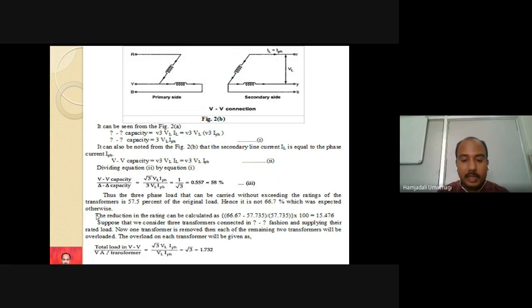Usually what we think is, suppose there are 3 transformers. If one of the transformers goes out of service, we will be under the mindset that 2 by 3 means 66.7%, so we say that it can carry 66.7% of the load safely, but that is not the case. If we check the capacity of delta-delta and open delta, then from the derivation you can prove that it can carry 58%, or else 57.7% of the load very safely, and it is not 66.7, right? Instead it will carry, on an average, 58% of the load very safely.